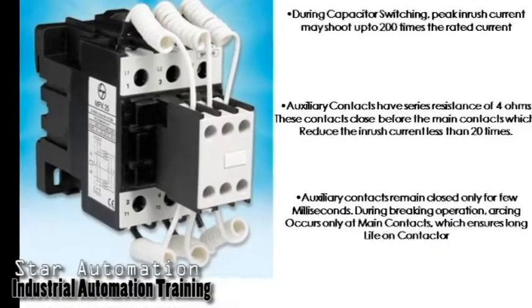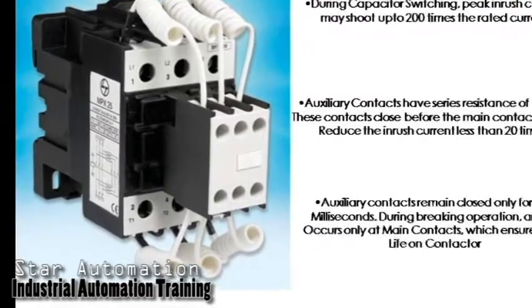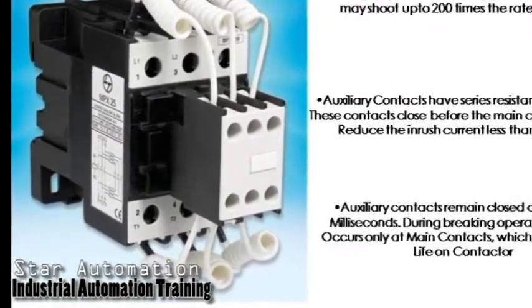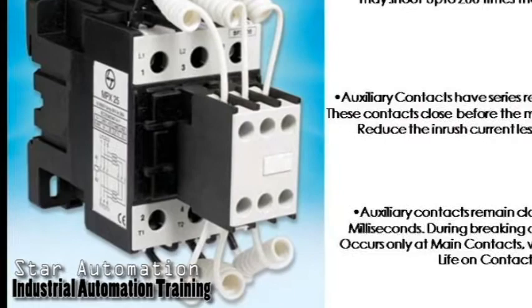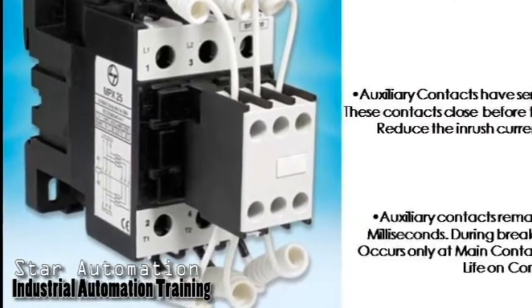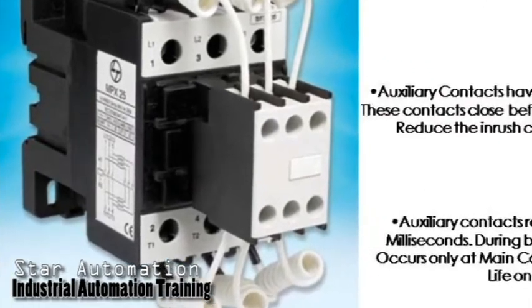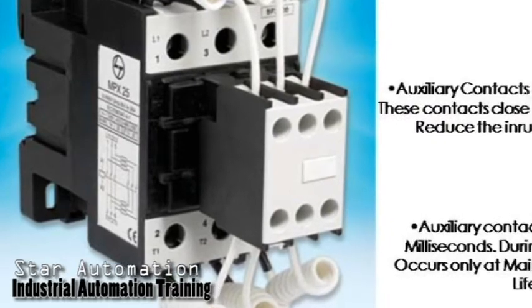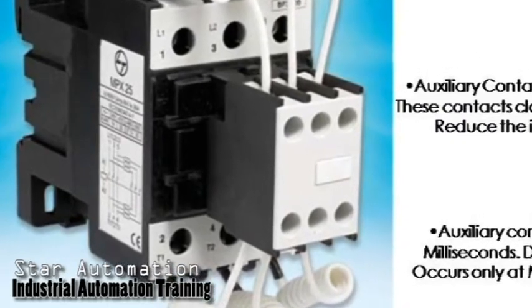Capacitor duty contactors are specially designed for capacitor switching applications. As capacitor switching is associated with high inrush current, the contactors are provided with damping resistors which limit the value of inrush current to a safe value.